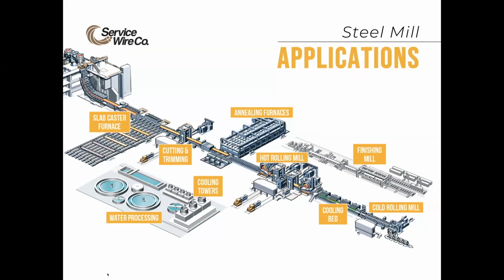Cables can be installed in a combination of conduits and cable trays to reach their final destination inside the facility. In many industrial applications, we're seeing more end users move to cable tray for ease of installation and lower install costs. The steel industry, however, continues to select cable design best suited for their manufacturing process over these inherent cost savings. Typically, they prefer to keep as much cable underground as possible to protect the cables from heat and physical damage. We could easily run 100,000 plus feet of singles in underground conduit to reach the process from the transformers.